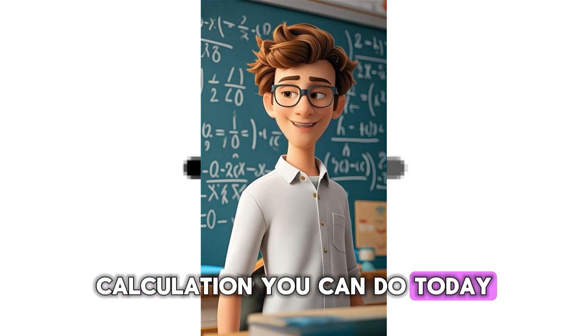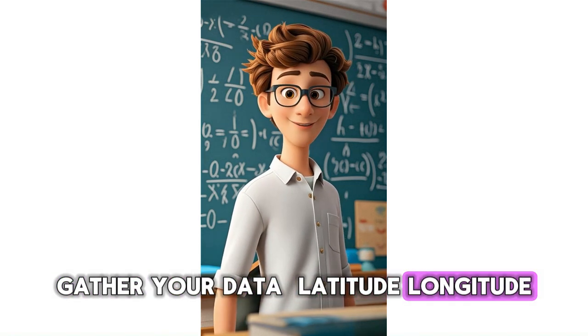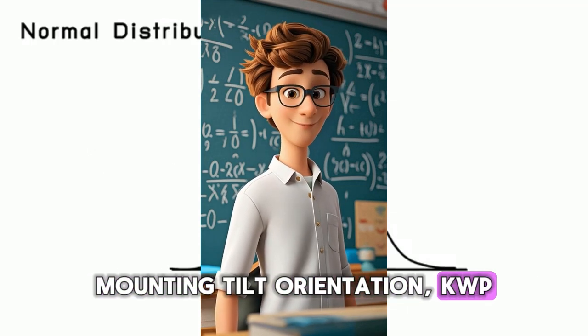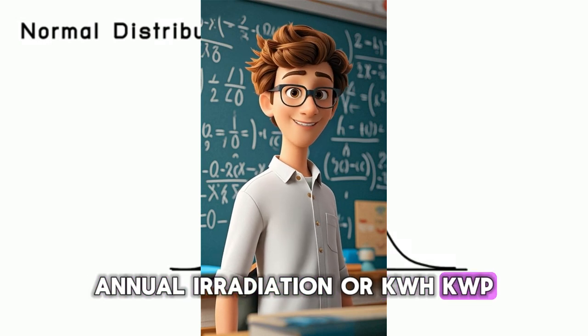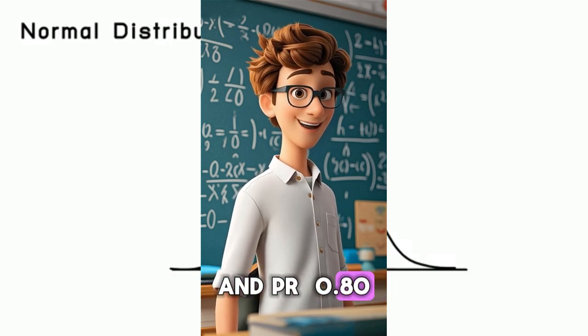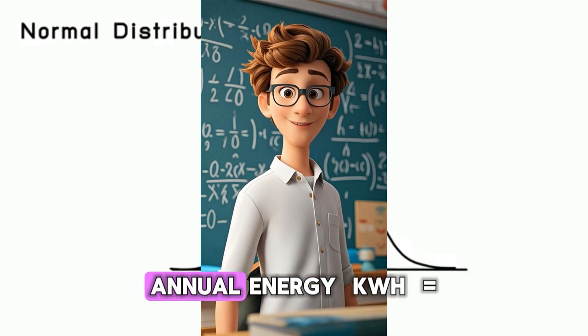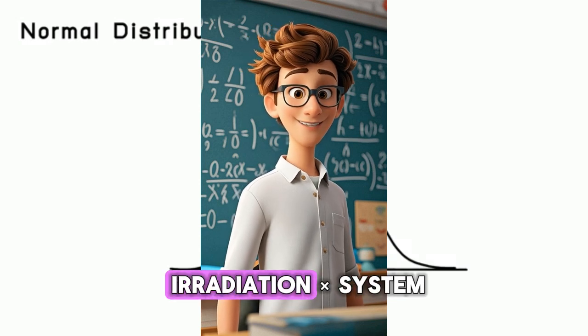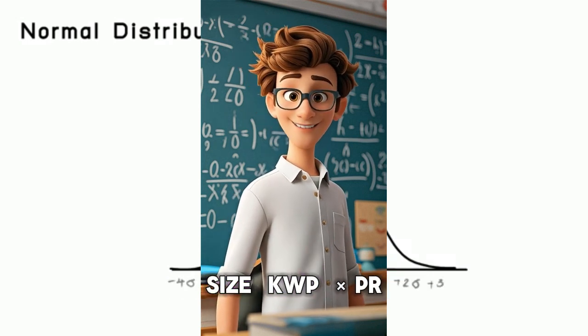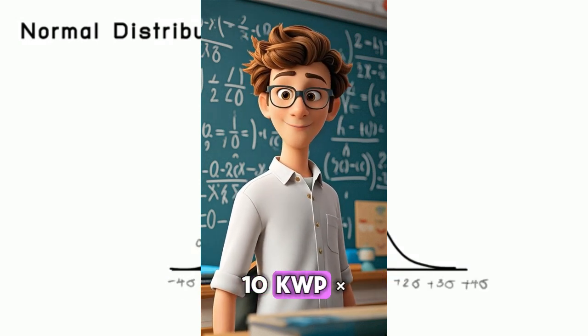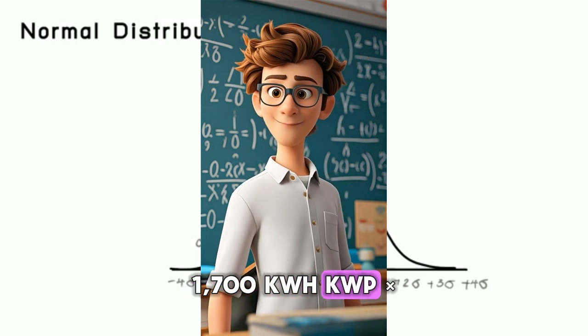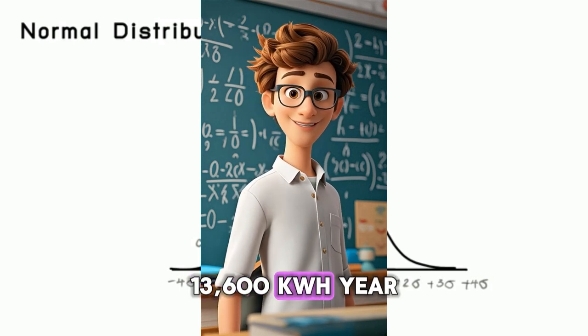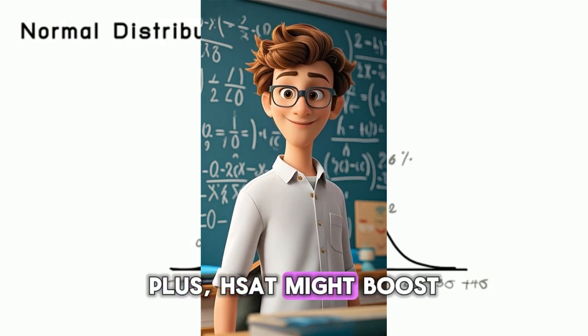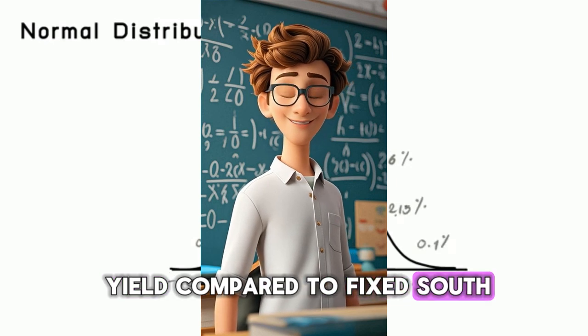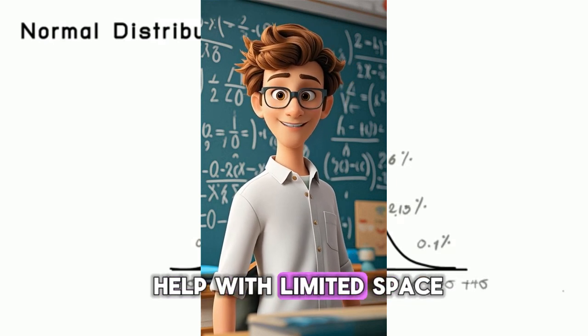Calculation you can do today. Gather your data: latitude, longitude, mounting tilt, orientation, kWp, annual irradiation or kWh/kWp, and PR, 0.80. The formula is simple. Annual energy, kWh, equals irradiation times system size, kWp, times PR. For example, 10 kWp x 1700 kWh/kWp x 0.80 equals 13,600 kWh per year. Plus, HSAT might boost yield compared to fixed south, and EW setups can help with limited space.